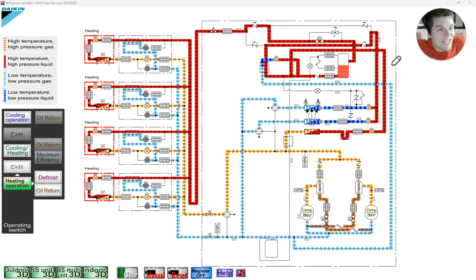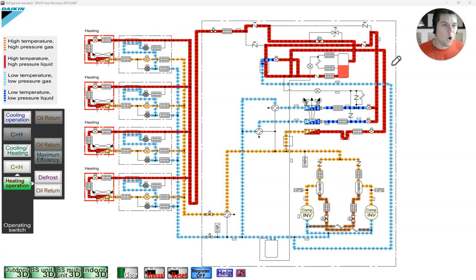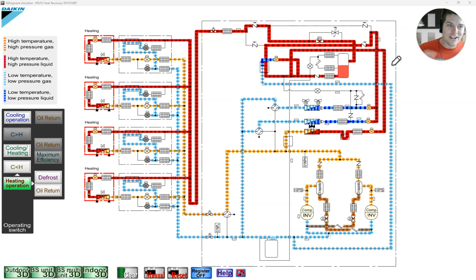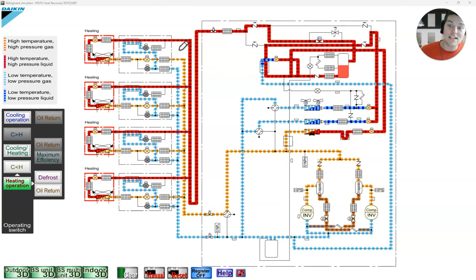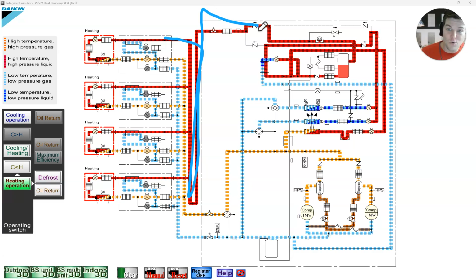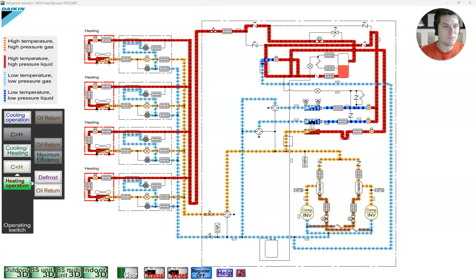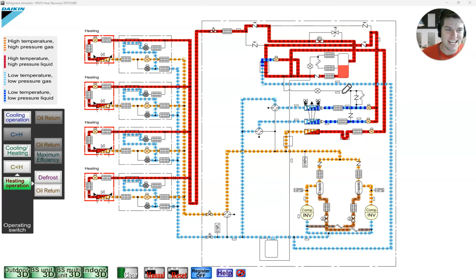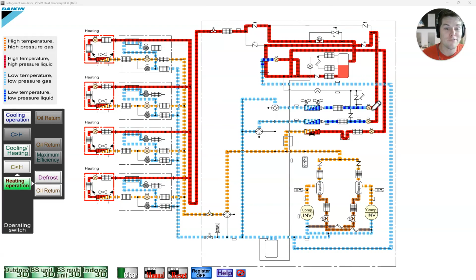What happens when a liquid turns to a vapor? It gets cold, right? It boils off and exchanges heat. It exchanges energy and temperature. That means that this liquid line is, guess what? Now a suction line. Your mind just blew. That's VRV and heating on low charge. And how do we confirm that?